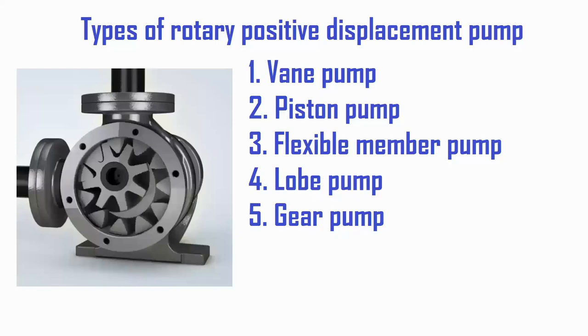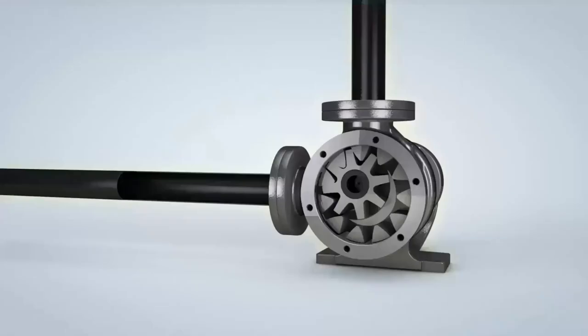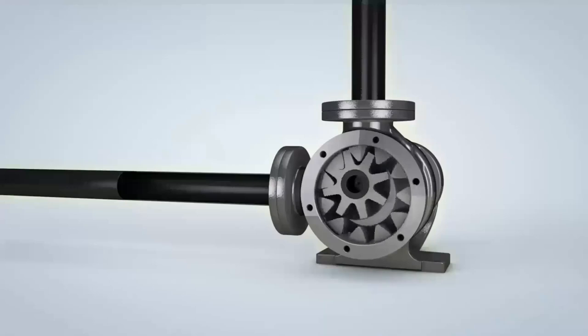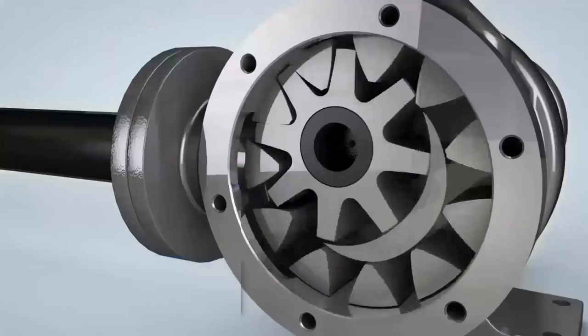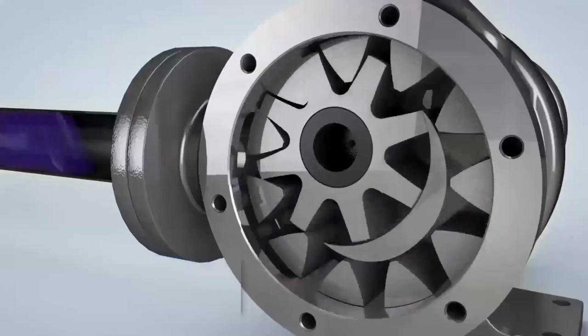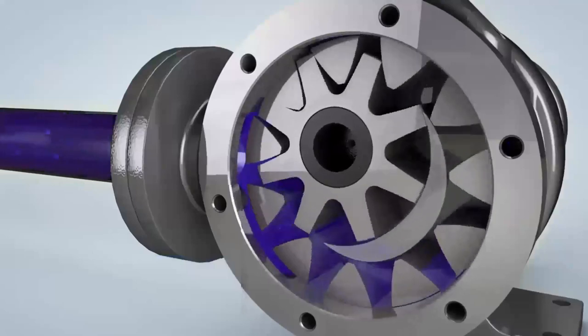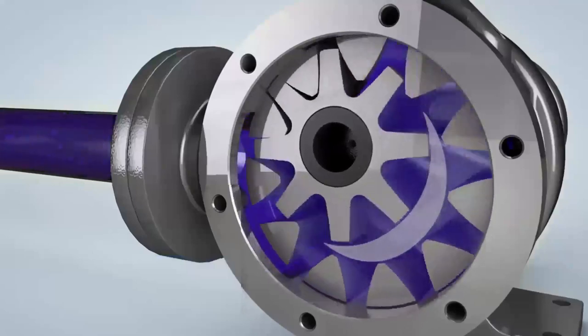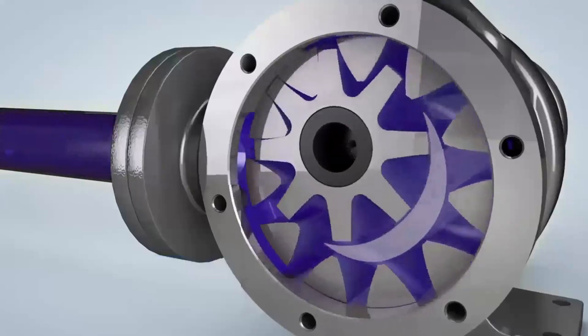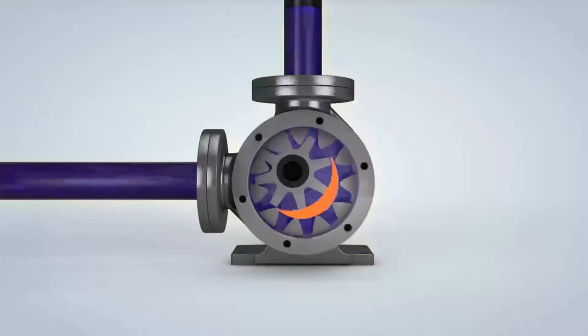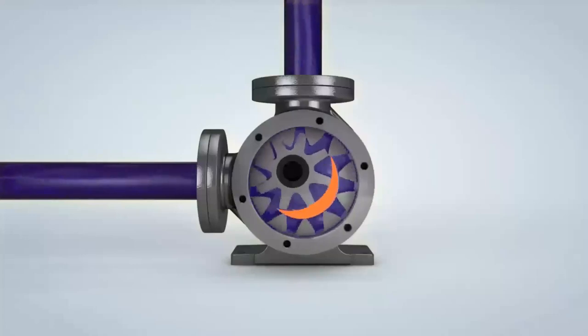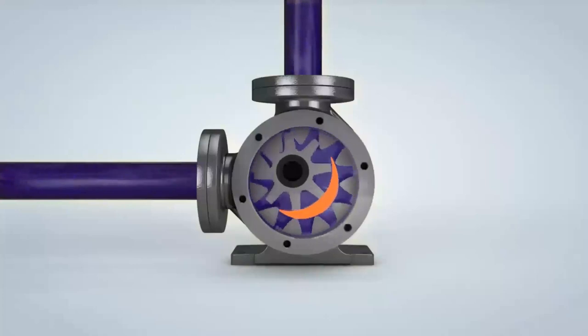The fifth type is the gear pump. A gear pump is a pump that uses two or more gears to move fluid. The sucked fluid is pressed from the fluid inlet side to the fluid discharge side using the cavity between two gears, or the cavity between a gear and the pump housing, while the gears rotate. Gear pumps are only suitable for pumping clean liquids without solid particulates, because particulates can cause wear on the gear surface.